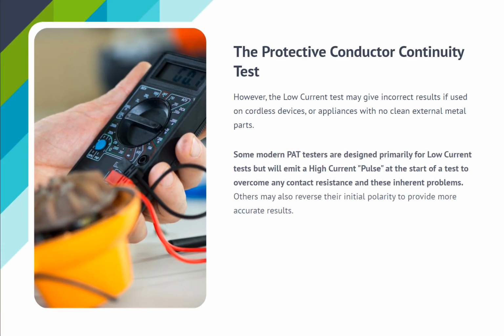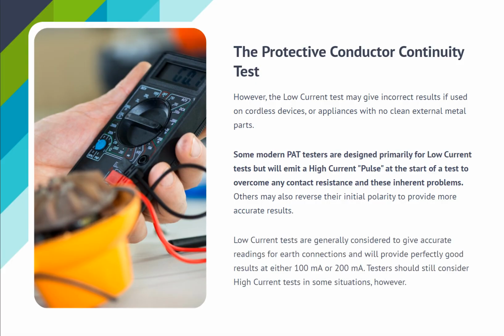However, the low current test may give incorrect results if used on cordless devices or appliances with no clean external metal parts. Some modern PAT testers are designed primarily for low current tests, but will emit a high current pulse at the start of a test to overcome any contact resistance and these inherent problems. Others may also reverse their initial polarity to provide more accurate results. Low current tests are generally considered to give accurate readings for earth connections and will provide perfectly good results at either 100 mA or 200 mA. Testers should still consider high current tests in some situations, however.